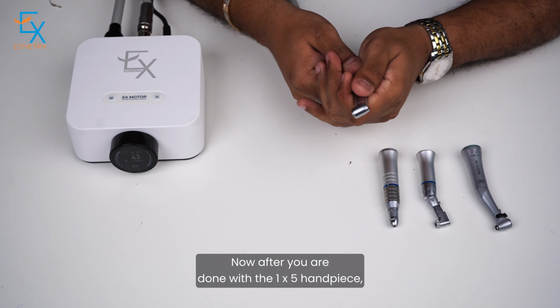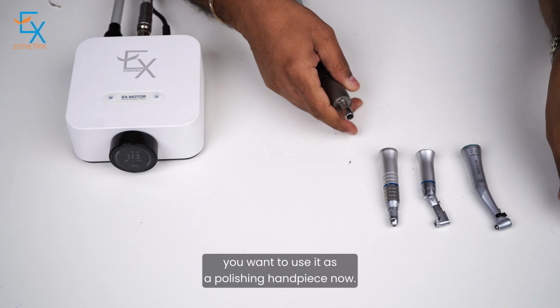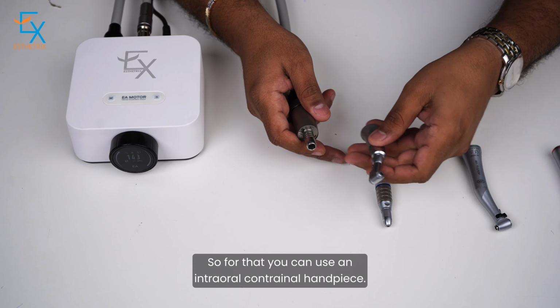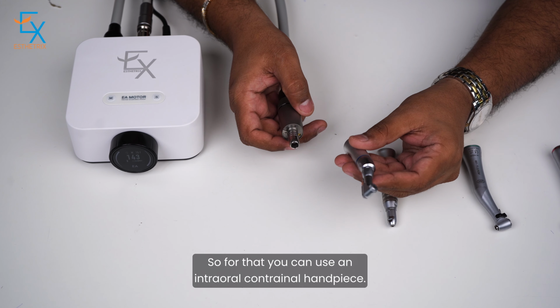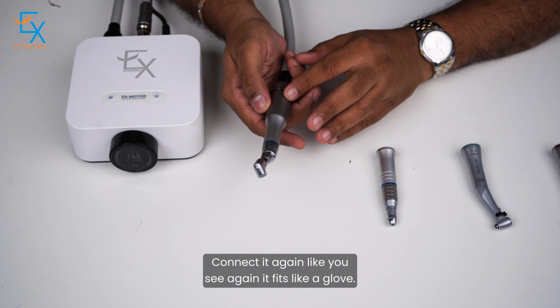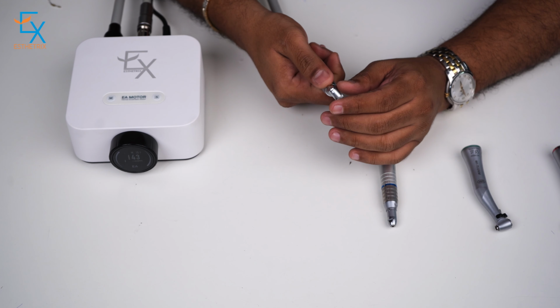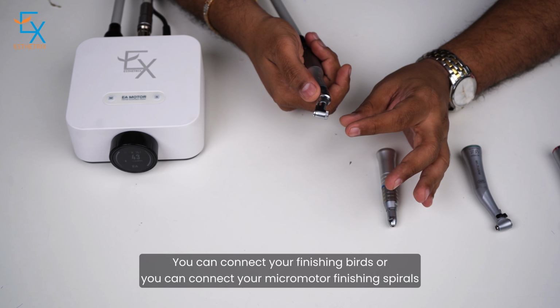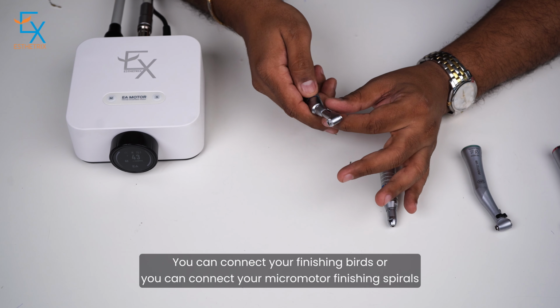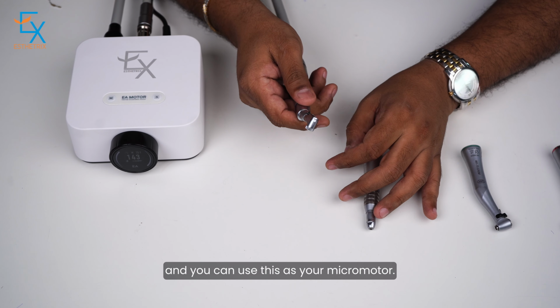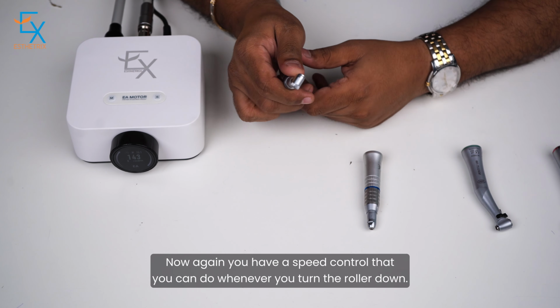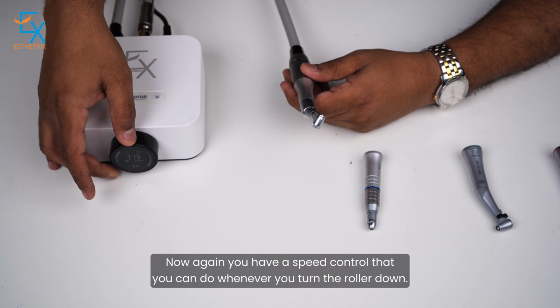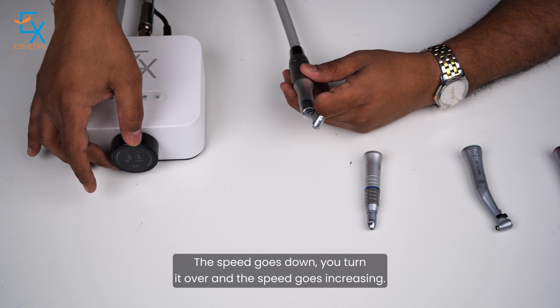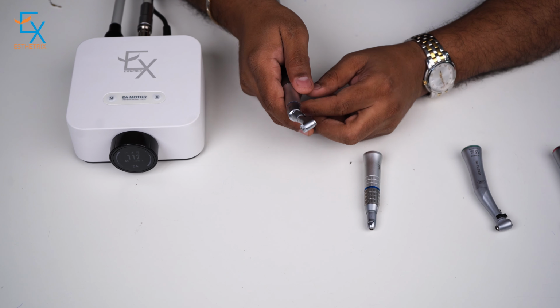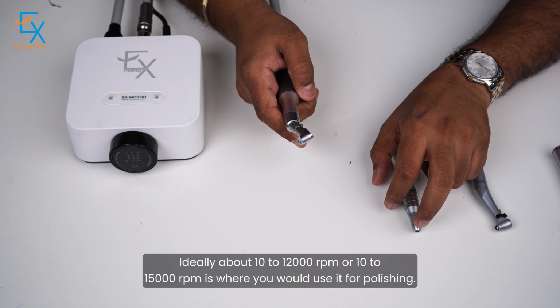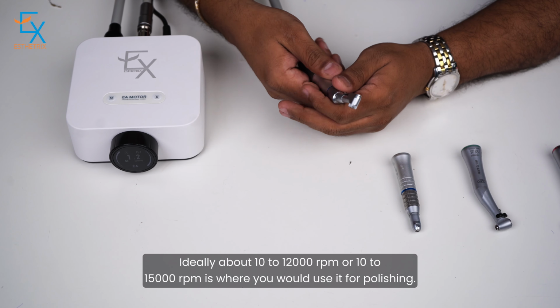Now after you are done with the 1:5 handpiece, you want to use it as a polishing handpiece now. So for that, you can use an intraoral contra-angle handpiece. Connect it again. Like you see, again it fits like a glove. There will not be any gap. You can connect your finishing burrs, or you can connect your micromotor finishing spirals, and you can use this as your micromotor. Now again, you have a speed control that you can do. Whenever you turn the roller down, the speed goes down, you turn it over and the speed goes increasing. Ideally about 10 to 12,000 RPM or 10 to 15,000 RPM is where you would use it for polishing.